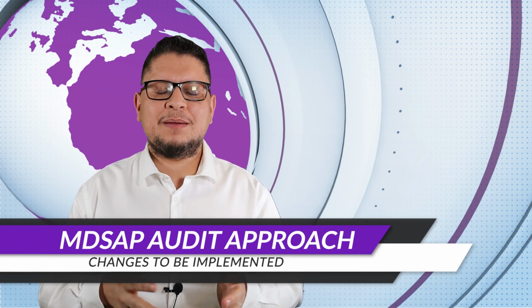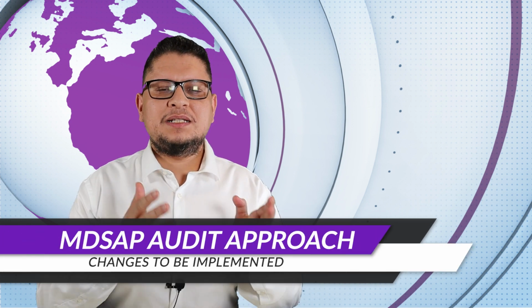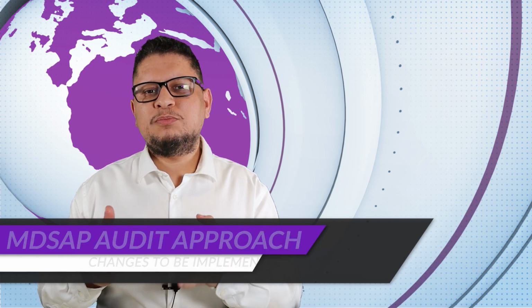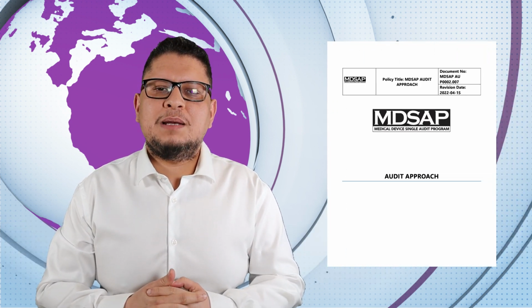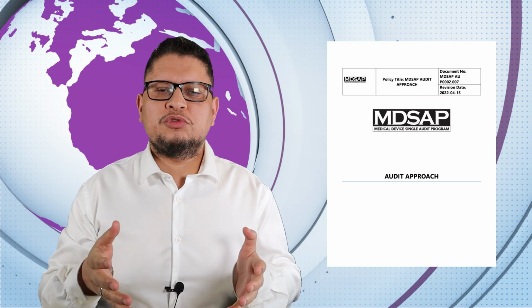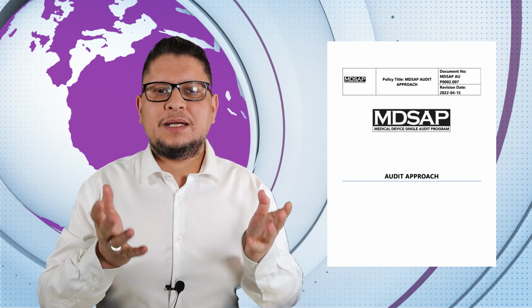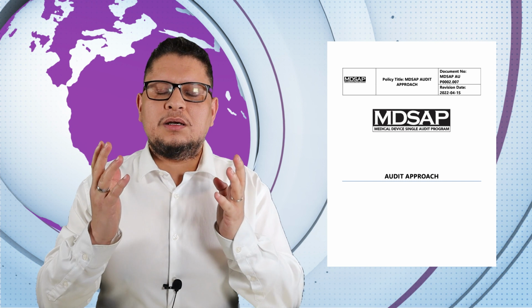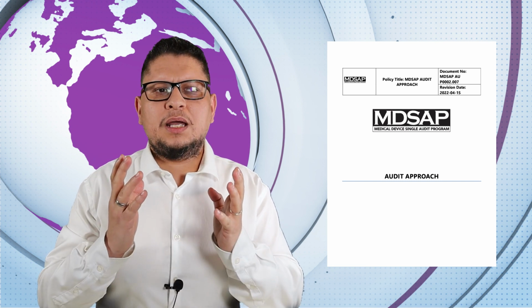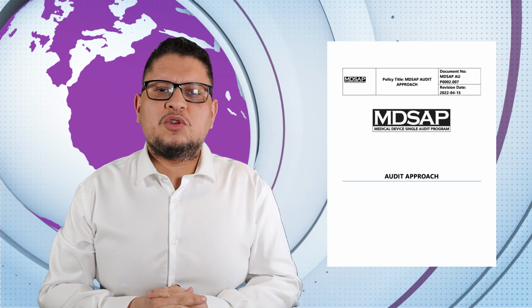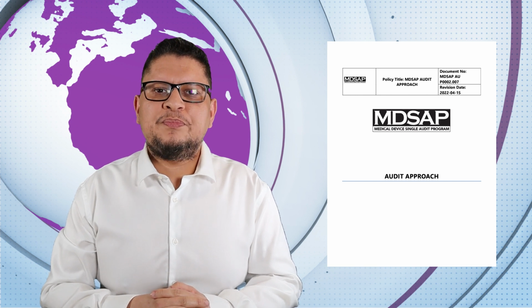Okay, let's go now to the US. So let's start first with MDSAP, the Medical Device Single Audit Program. This is a program that helps you to register your products within 5 countries: Canada, USA, Brazil, Japan, and Australia. So these are the countries that are covered within MDSAP.